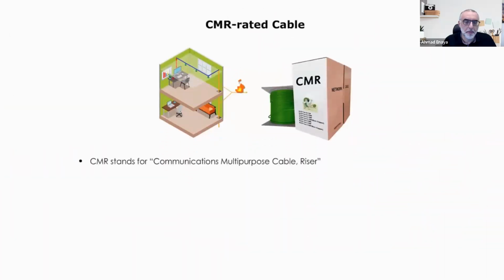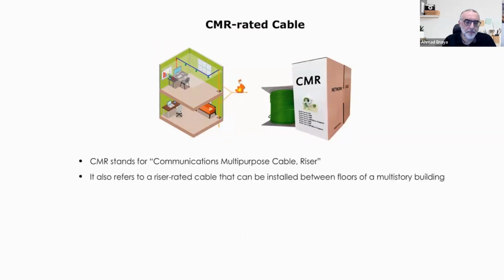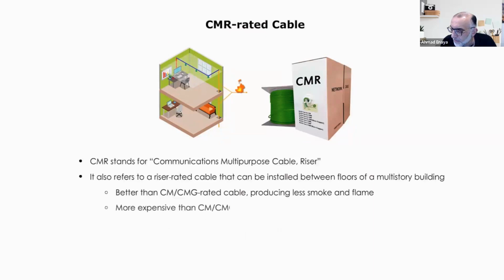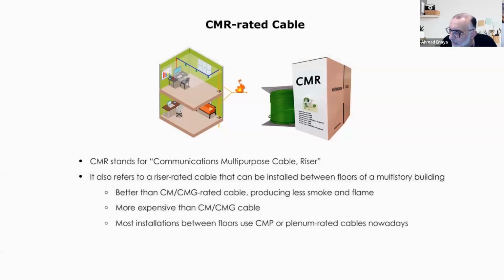CMR stands for Communications Multi-Purpose Cable Riser. It also refers to the riser-rated cable that can be installed between floors of a multi-story building. It's better than CMG-rated cable, producing less smoke and less flame, but it's more expensive than CM or CMG cable. Most installations between floors of a building use CMP or plenum-rated cables nowadays.